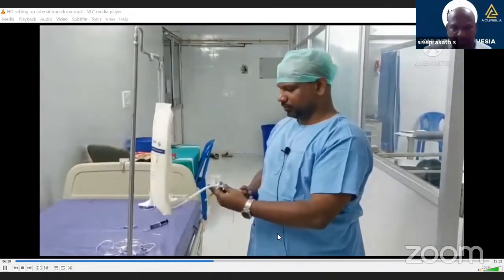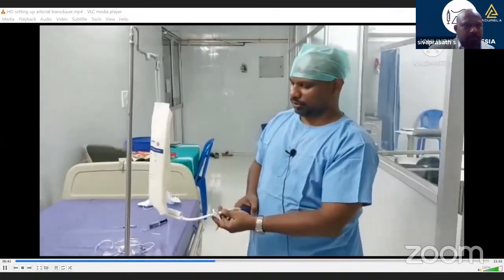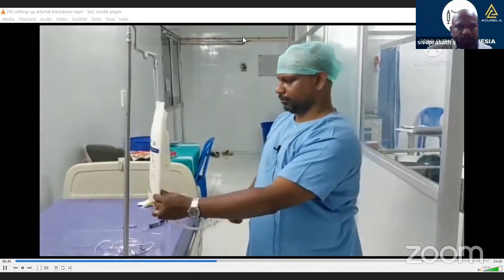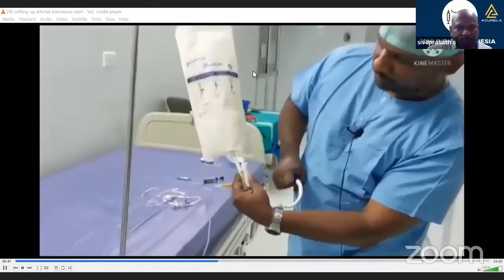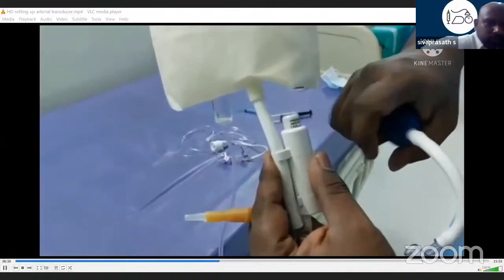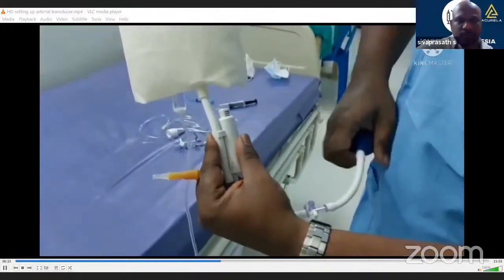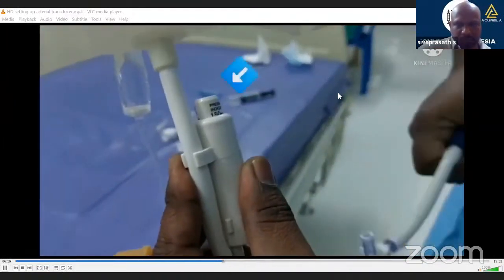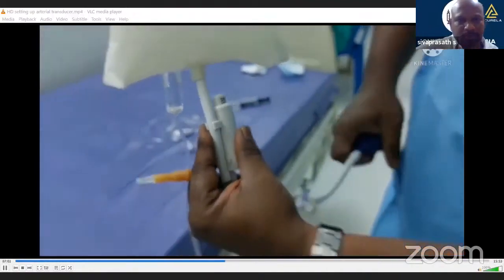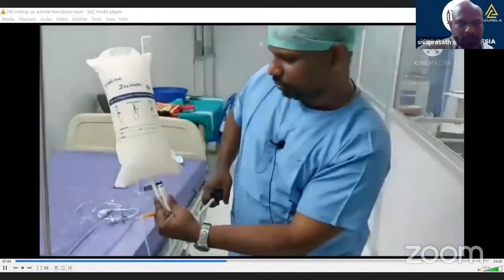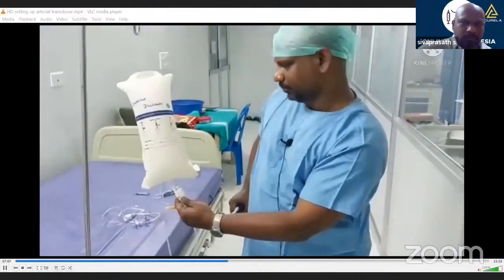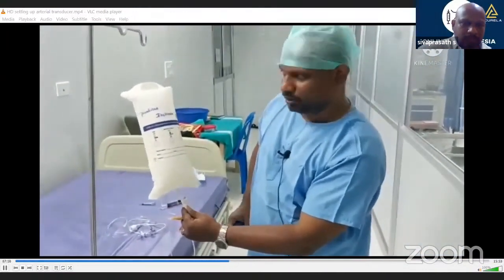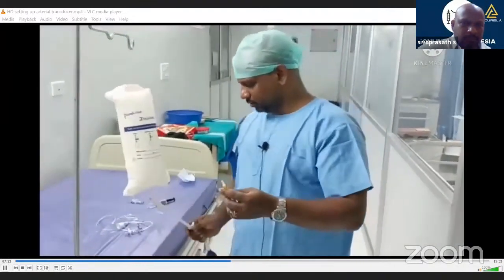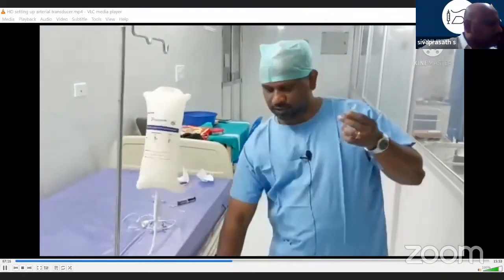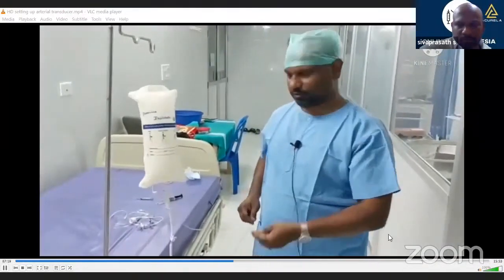So what we do is, here also it contains a stopcock. Turn it towards here. You can see here there is a pressure monitoring system. Slowly it's rising. Because it's a collapsible bag, it takes slightly more time. And now it's at 300 millimeters of mercury. Close this. If I just open this, you can see fluid will jet out.